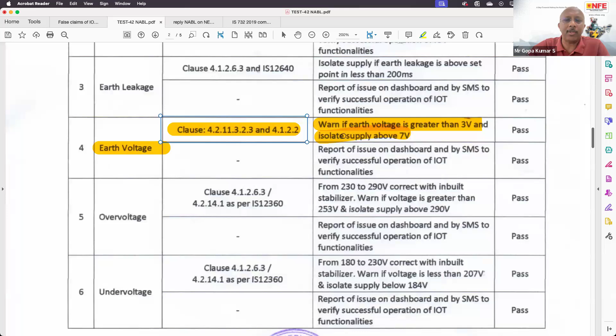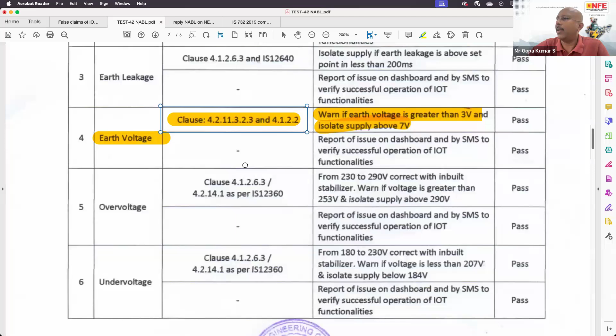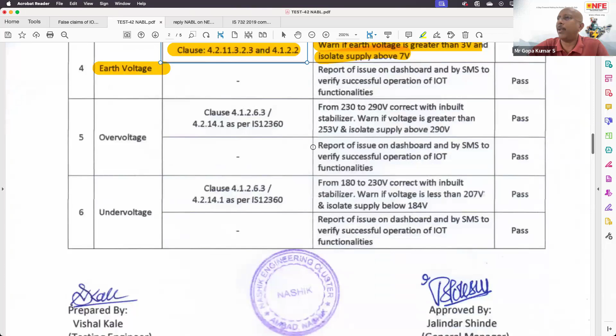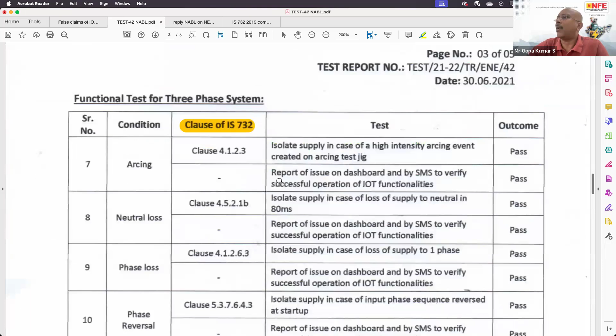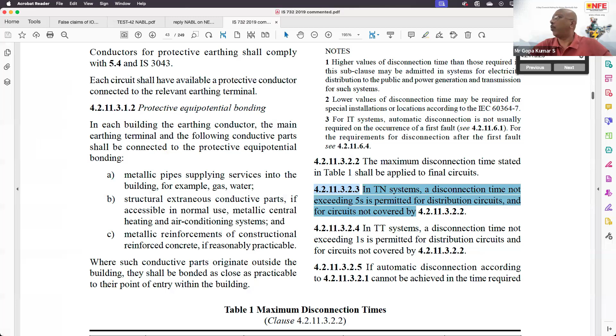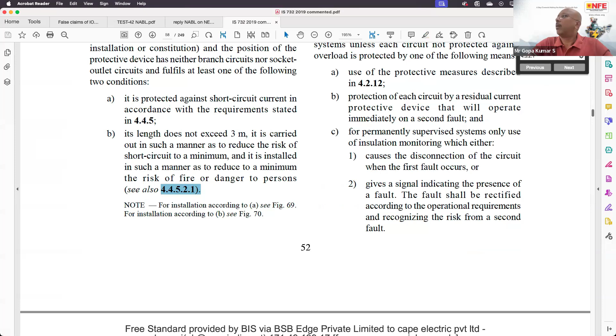IS 732 says that for main circuits, you can go up to 5 seconds disconnection. Here it is talking about something totally not at all in relation. So like this, if we go through each and every parameter of this test report, like over voltage, under voltage, all these parameters are totally different. Now, let's say neutral loss, serial number 8, clause 4.5.2.1. Let me take 4.5.2.1.